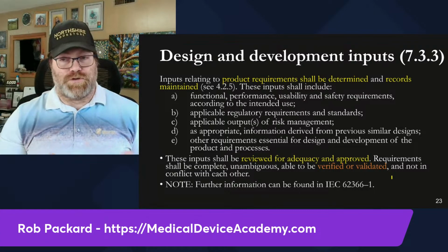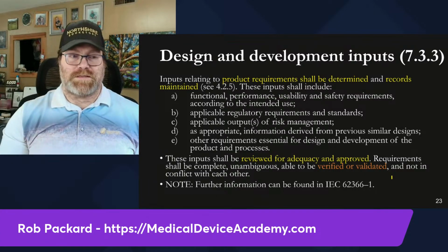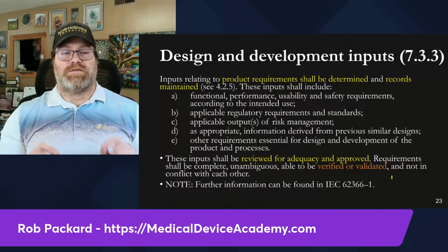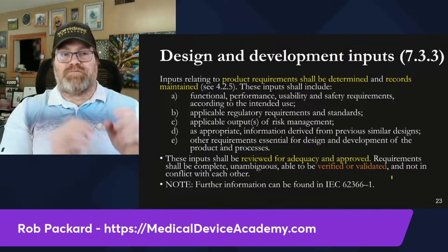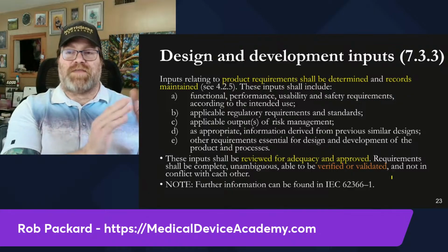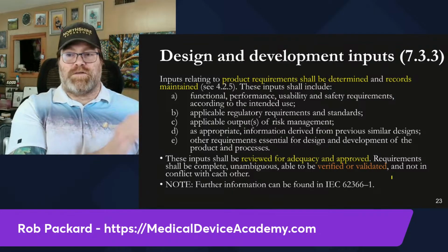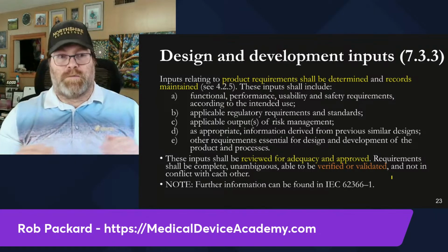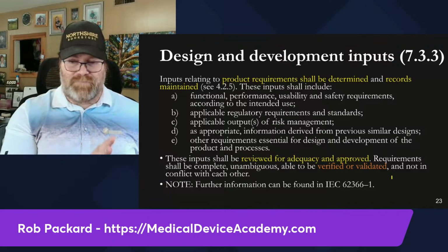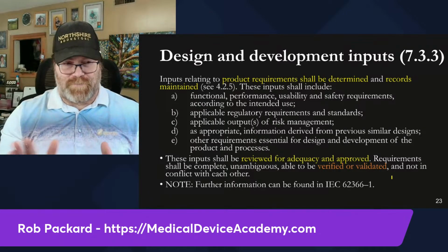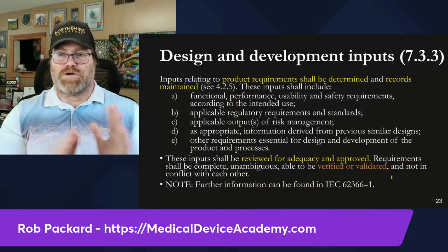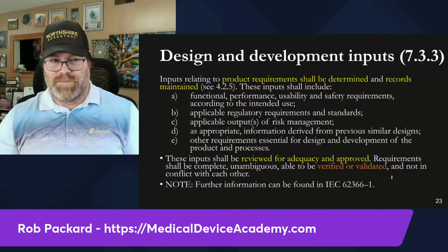It's possible you could do both, but most of the time, you're not doing both. So these people that have the preconception that for every single design input, I have to have a user need that I'm going to validate, that's wrong. You were misled by the very bad, evil waterfall diagram. It misled you. You fell for that trap. Do not create a user need for every input.